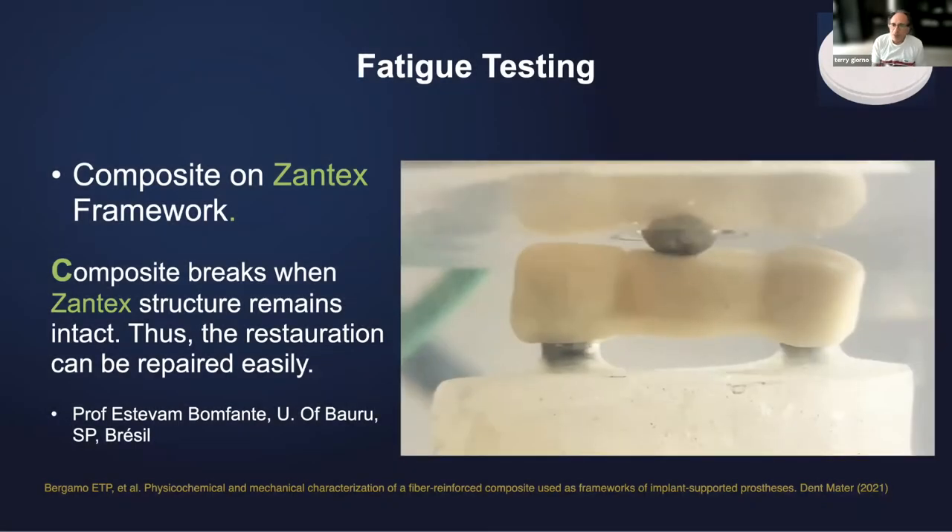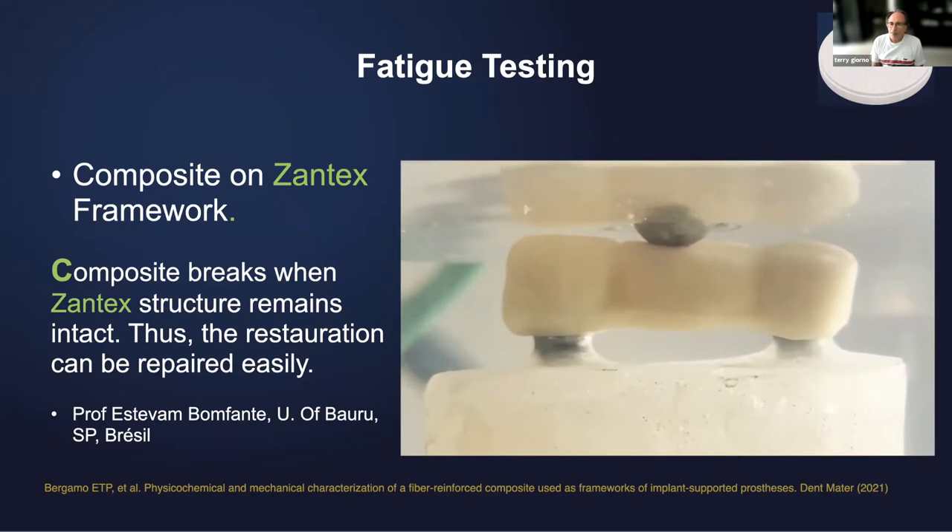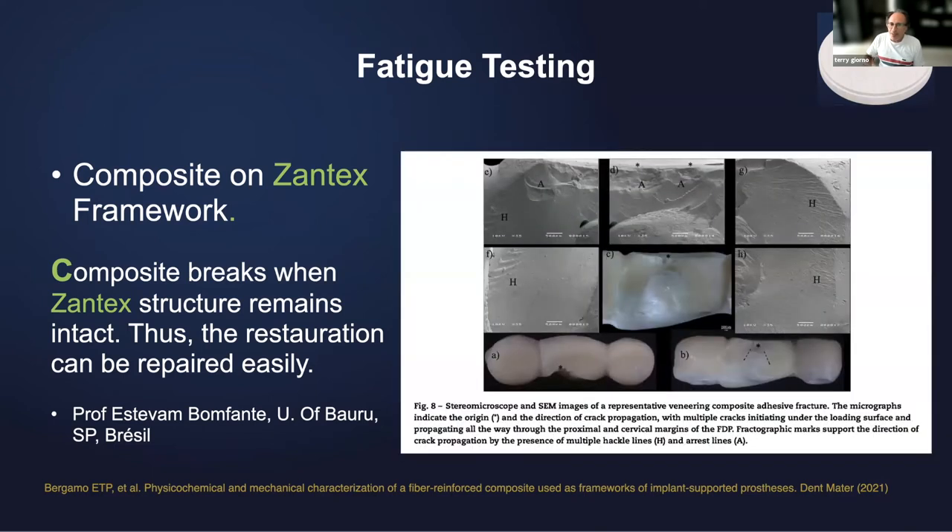This is testing that has been done in order to write this paper. Here you have two implants — you have a Zantex framework which is veneered with some composite, and you have a fatigue study that goes onto a machine at five hertz, bumping onto that thing until it breaks. And the good news is that when it breaks, the composite breaks but not the Zantex — the framework is untouched. Obviously, it makes it very easy to repair; it's just a matter of repairing the composite. The framework is untouched.